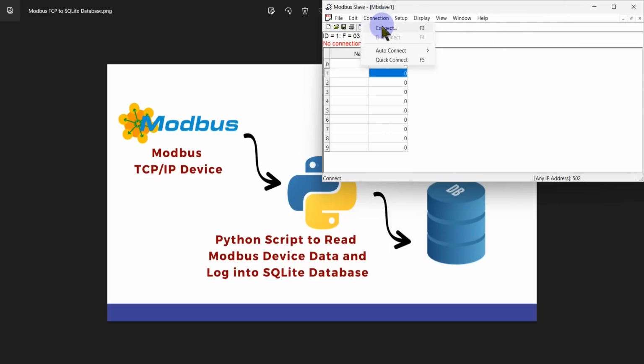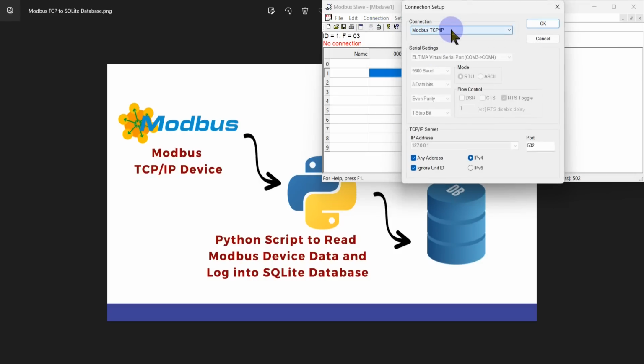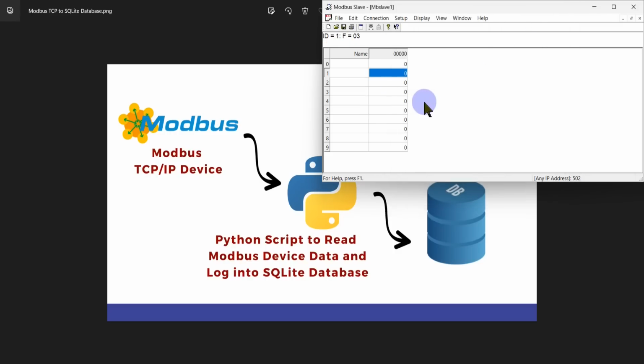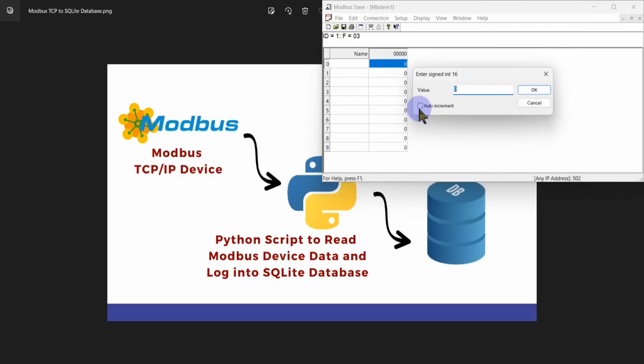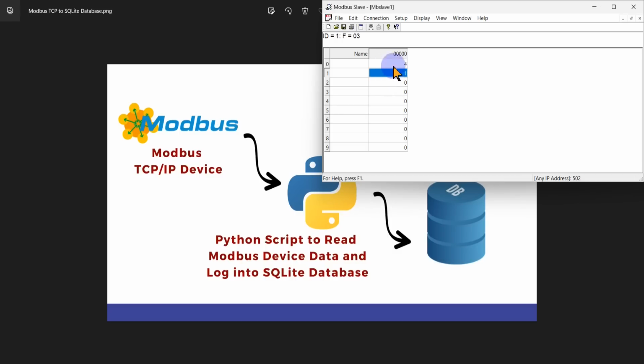Then I press OK, go to Connection, and choose Connect. Then I choose the connection type, which is Modbus TCP/IP. The port number is 502 and the IP address is 127.0.0.1. If I press OK, our Modbus TCP device is started. I can simulate the values by using the auto increment function here. You can see the value is auto incrementing at a certain rate.